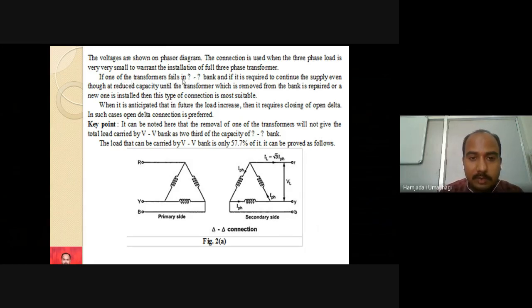If one of the transformers in a delta bank fails, and it is required to continue the supply even at reduced capacity until the transformer which is removed from the bank is repaired or a new one is installed, then this type of connection is most suitable. So suppose there is a fault in the delta connection and one transformer goes out of service. In that case, the other two single phase transformers, now connected in open delta, are ready to serve the electrical load very effectively until the third phase transformer gets repaired or a new transformer is reinstalled.